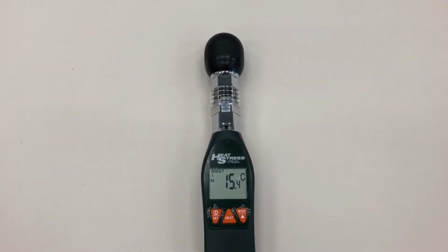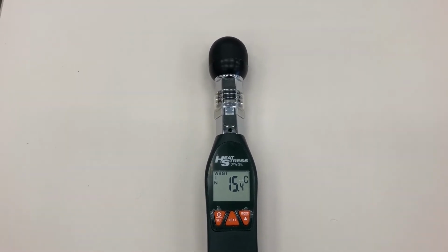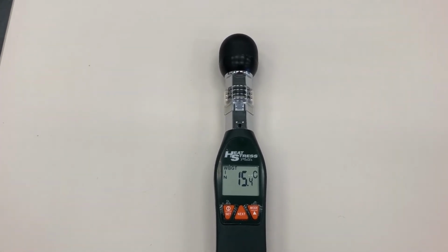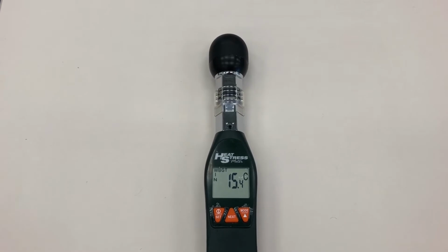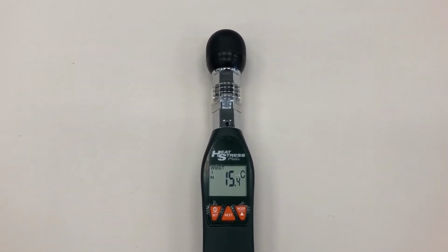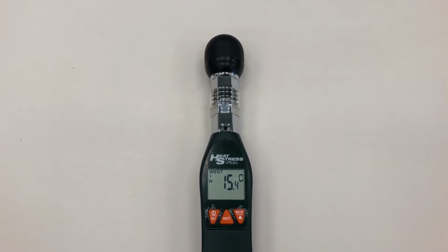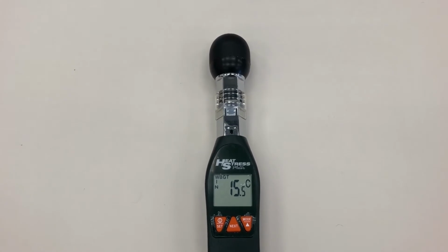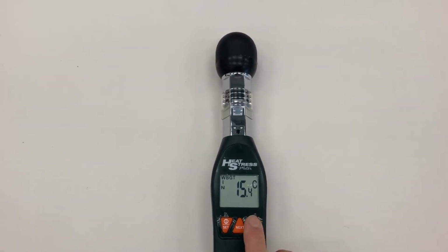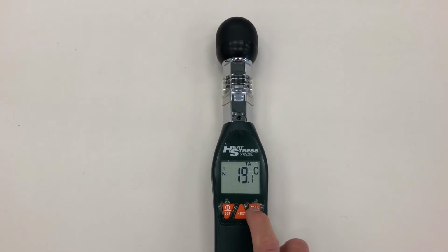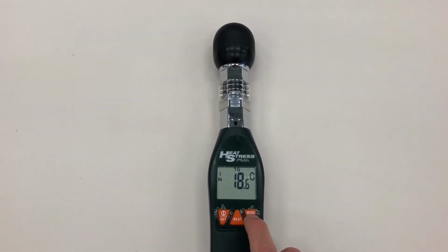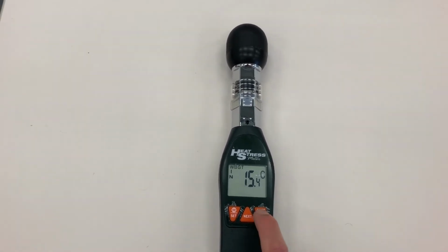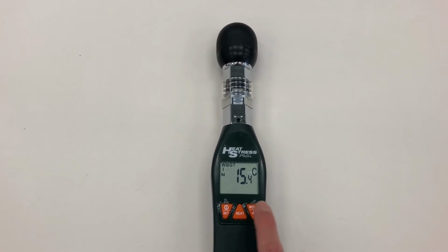And so if you have low relative humidity, that is going to mean that you're taking the dry bulb temp minus the wet bulb temp, and the difference is high. High relative humidity would be the dry bulb temp minus the wet bulb temp, and the difference would be low, and it's just looking at the weighted average overall of the dry bulb temp, the wet bulb temp, and the globe temperature. So you can just toggle back and forth between all the measures, and it also has the relative humidity there as well, and obviously the temperature.